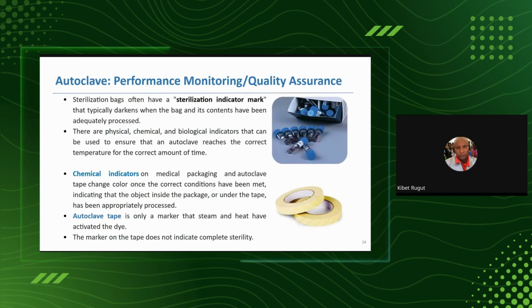There are also indicators that are called biological, and it also ensures that it has reached the correct temperature and time. Chemical indicators on the medical packaging and autoclaves change color. So at least all of us have seen this method being used to verify the sterilization process. It just shows that it has completed the cycle. So also learn to read the instructions of any item that you use to verify your sterilization system.